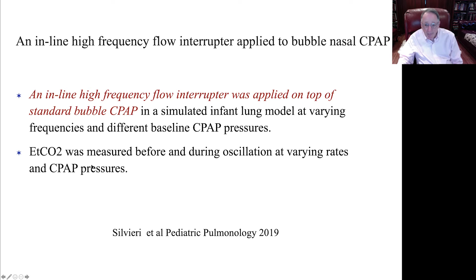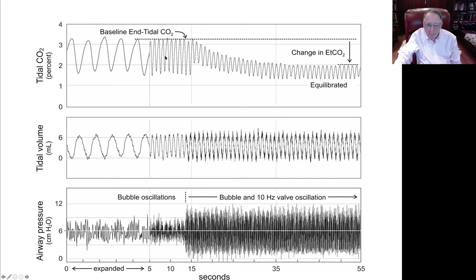And here's when you put on the bubble oscillations plus the oscillator, you can see the frequency and amplitude of those oscillations is much greater. But in fact, tidal volume was actually not greater, but end-tidal CO2 markedly came down from use of bubble CPAP down to where the high frequency flow interrupter was used. And when they looked at varying CPAP pressures, which are shown at the bottom of this picture, 4, 6, and 8, and then varying frequencies of the high frequency flow interrupter, the best frequency for producing the maximum removal of CO2 was 10 Hertz.